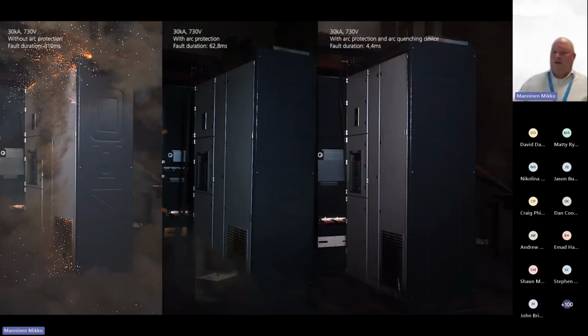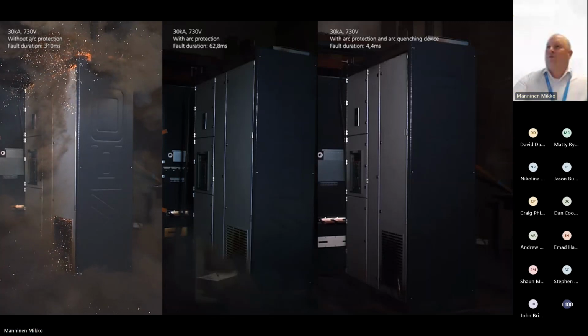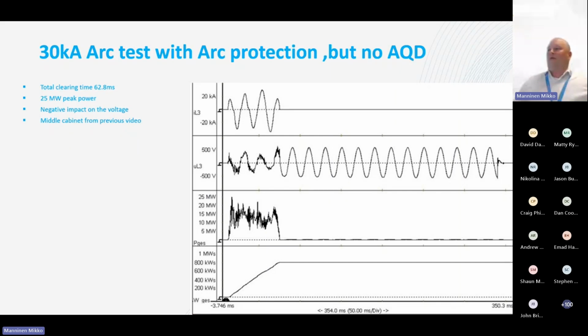It is quite a massive difference. I can also tell the difference from these oscillographs. So again, this is now 30 kiloamps. This is the smallest power test we did, 30 kiloamps, which is practically nothing today. It is a big amount of current, yes, but today the trend seems to be that 30 kiloamps is nothing anymore. The typical current levels are getting closer to 50, 65, 80, and 100.